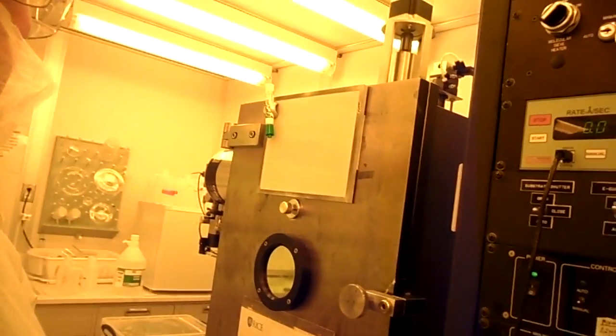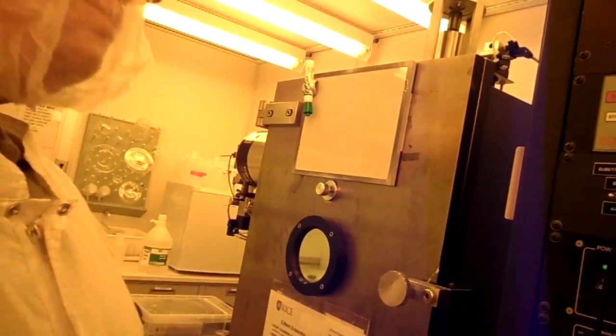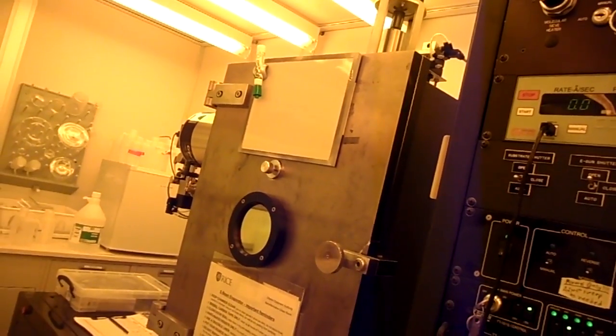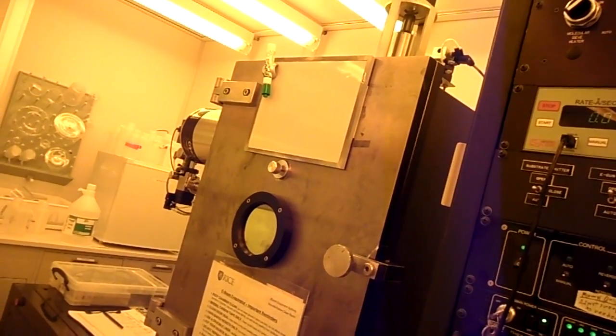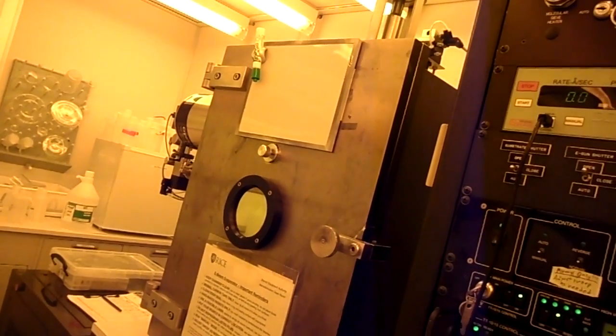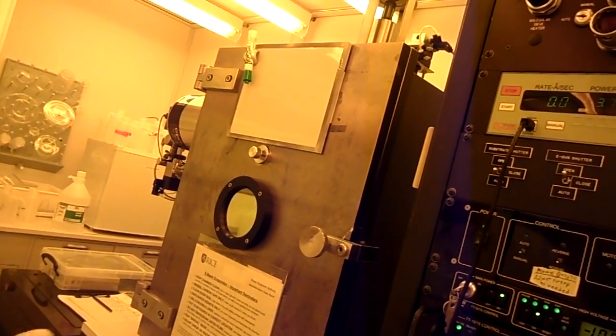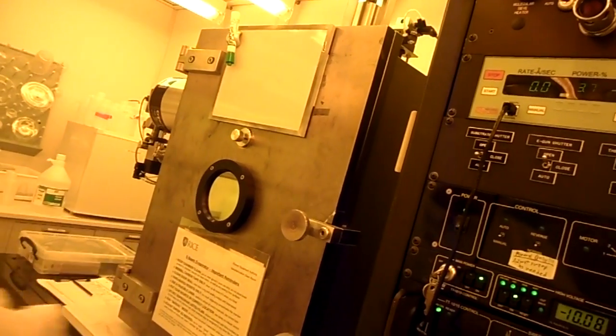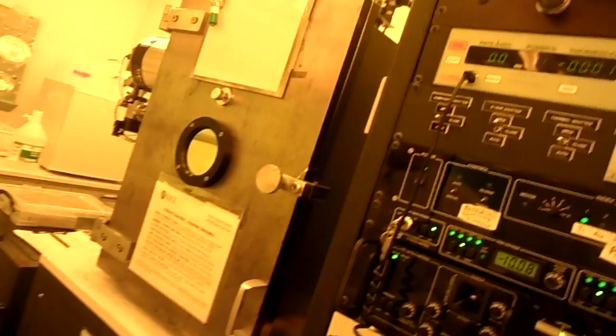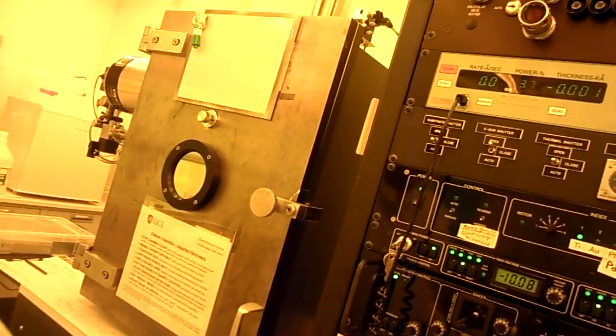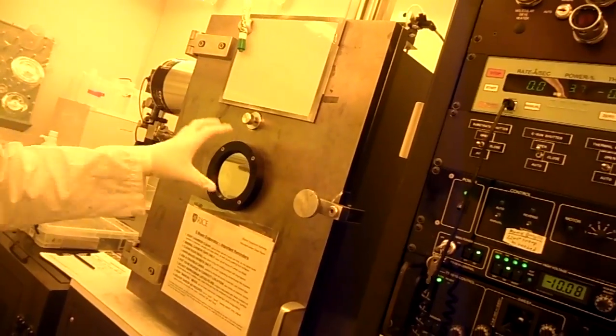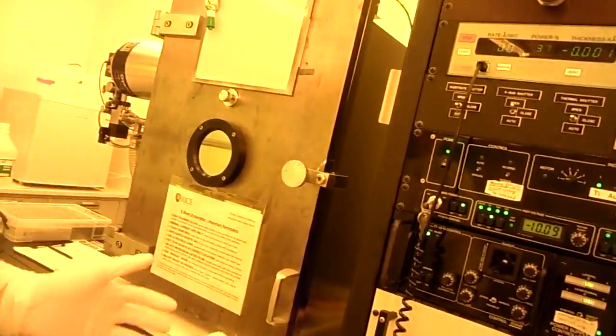If power is higher than you need, you're going to get a really fast rate, which may not be good. If you want a higher quality film, a slightly lower deposition rate is good. But if you're doing a very thick film, that's not as important. But if you're doing a thin film, you want a slow rate because that relates to your quality. If it's not high enough power, you won't get any rate at all. It'll just be glowing, but it won't be completely melted, and therefore it won't evaporate. So there's hot, and then there's melted. We need to get to melted before it will evaporate.